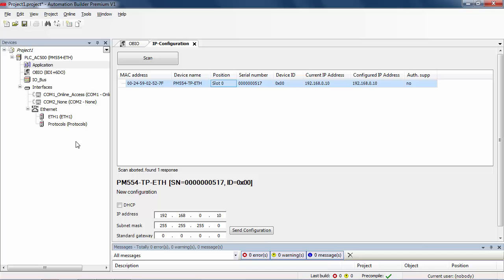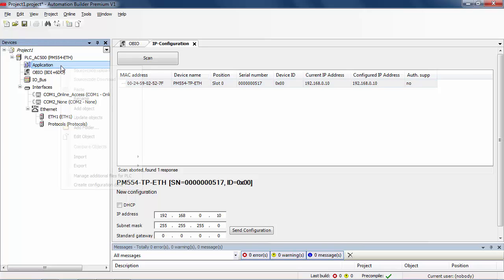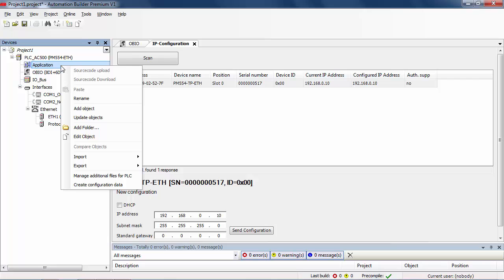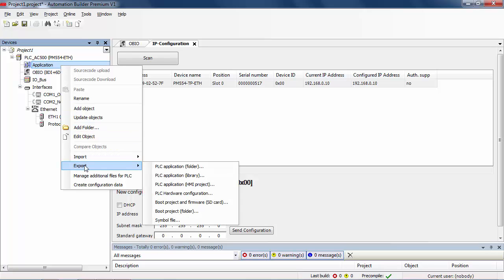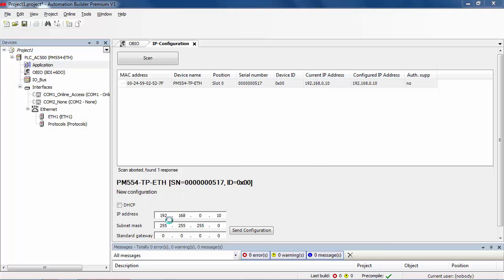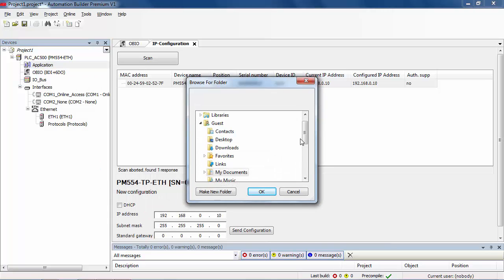After completing the configuration, return to Automation Builder environment in order to export the symbol file and allow to import it in Panel Builder 600 Basic. Right-click on application object, select export and then symbol file, and finally save it in a designated folder on your disk.